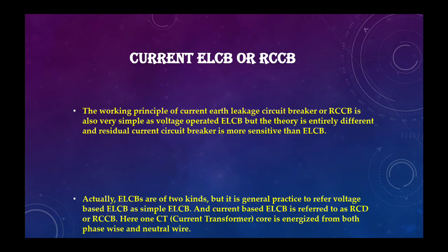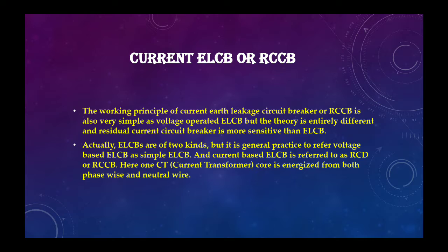Now the next slide is the current ELCB or residual current circuit breaker, RCCB. So what is RCCB? The working principle of current earth leakage circuit breaker or RCCB is also very simple, as voltage operated ELCB. But the theory is entirely different, and residual current circuit breaker is more sensitive than the ELCB. Actually, ELCBs are of two kinds, but it is general practice to refer to voltage-based ELCB as simple ELCB, and current-based ELCB is referred to as RCD or RCCB.